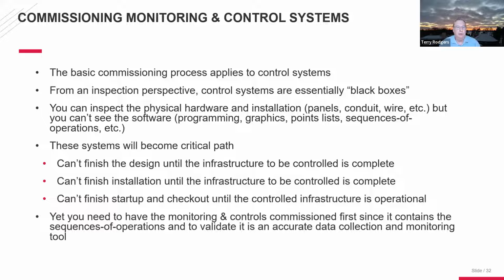The basic commissioning process applies to control systems just like it would to a chiller or any other system. From an inspection perspective, these things are black boxes. As a commissioning agent, I walk in the field and can see progress on chiller installation, conduit, switch gear, all this stuff. But I look at the BAS system and see a panel, some wires running into it, maybe lights on or blinking, but that's as far as I can tell looking at it. The sequences, the logic, the critically important stuff is software running inside that panel.